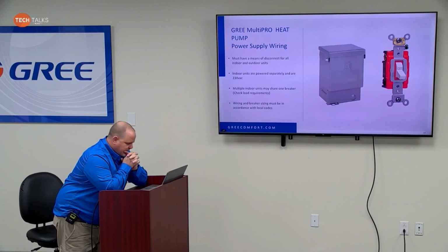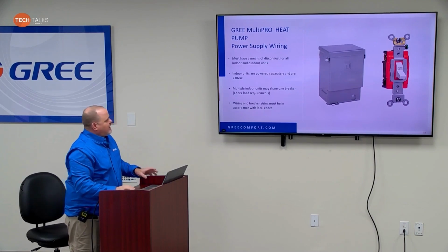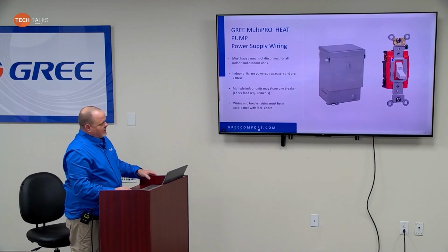So the indoor units. All of the indoor units with MultiPRO are 230 volt power supplied. There are no 120 volt options for indoor units. We do recommend that you have a means of disconnect, because you can have 4 wall mounts or 4 cassettes, even possibly 4 ducted units, all on one 15 amp 230 volt circuit. But when you're there to service the system, you don't want to have to turn off power to all of them at once. So a means of disconnect at those indoor units is highly recommended. It does not have to be an AC disconnect like you see here. It can simply be a 15 amp 2-pole switch, as long as we're killing power to both L1 and L2, so it's safe to get our hands in there and work on the machine.